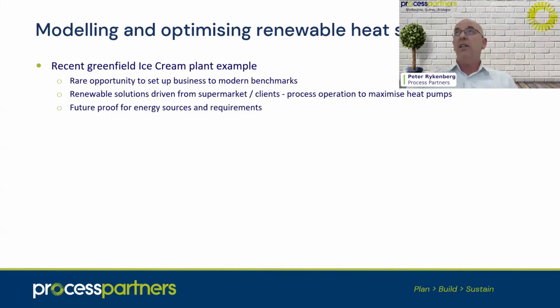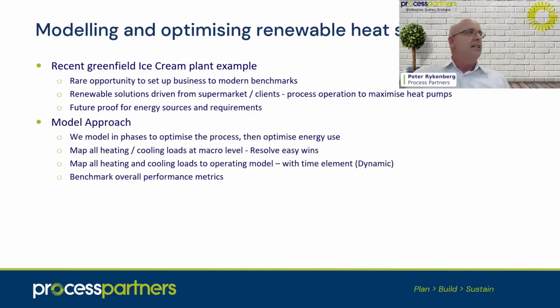And as you said, Jarrod, as far as I'm aware, this in the dairy industry is the first implementation where we've got no steam boilers. All our process heat source is all from heat pumps. Given it was a greenfield project and there was a real clear directive from the client and very much driven by the marketplace to drive this as quite a game changer in terms of carbon footprint for a facility, the driver was definitely there.